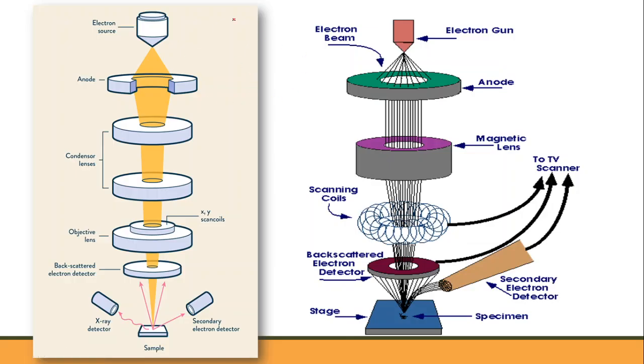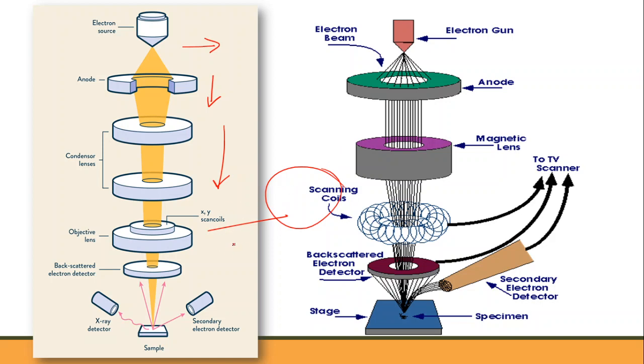In the SEM setup, the electron gun produces the electron beam by heating a tungsten wire with current. This beam is accelerated by the anode, then travels through electromagnetic fields and lenses which focus the beam toward the sample. Scanning coils then deflect the beam so that it scans across the surface of the sample in a rectangular frame.